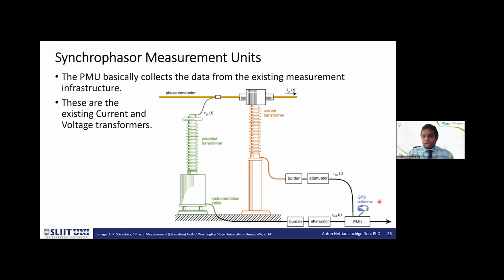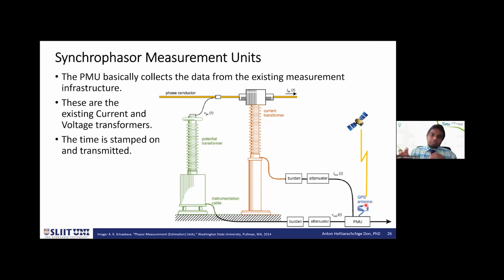And then you also have a GPS antenna within the PMU. This gets its GPS signal, and I'll talk about what this signal is. Using the GPS signal, they put a timestamp on this information and transmit it out through their communication network. That's essentially what the PMU does. The point here being that it's able to do it at a very fast rate compared to the traditional system. That's one of the advantages.